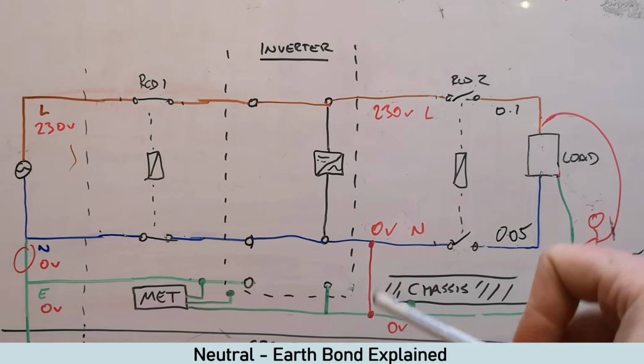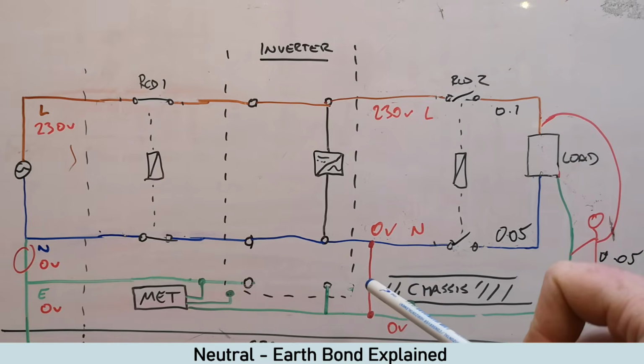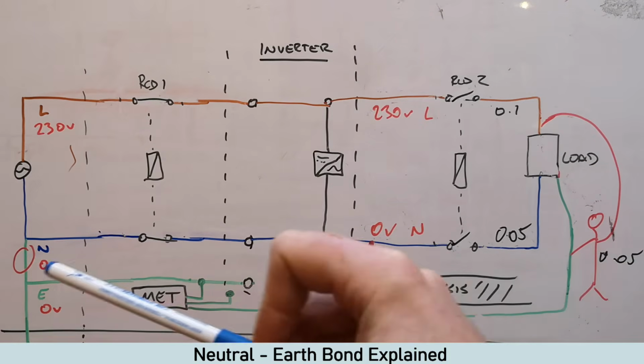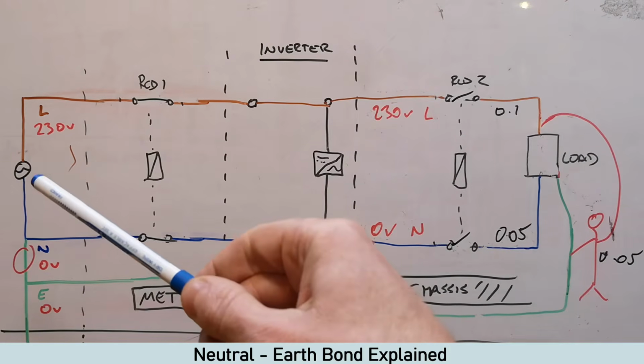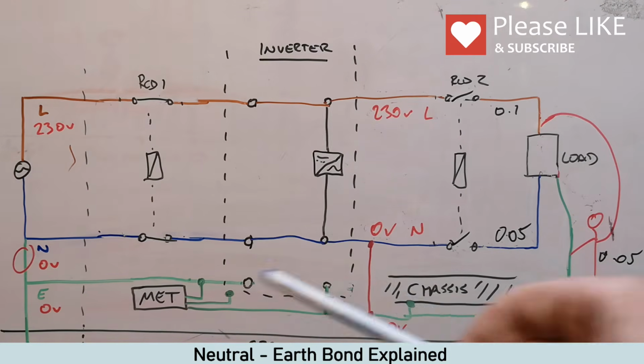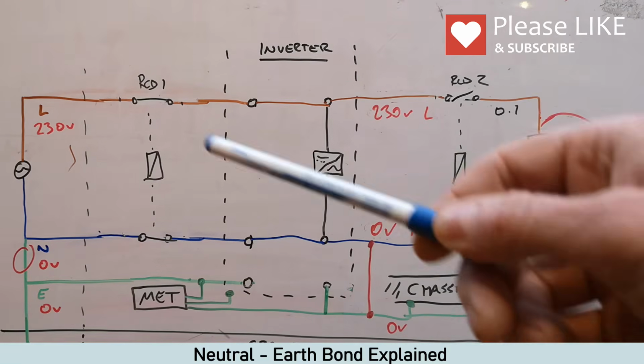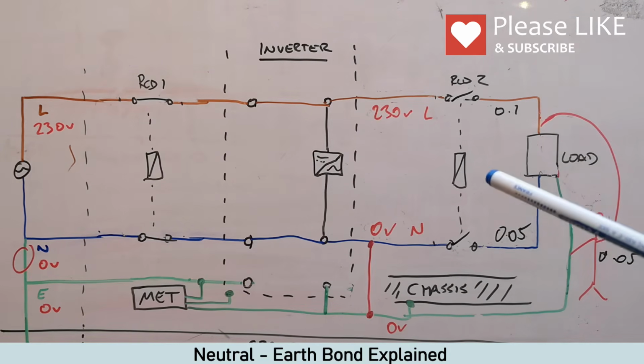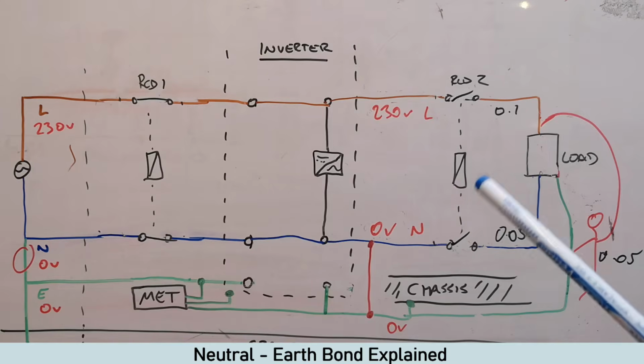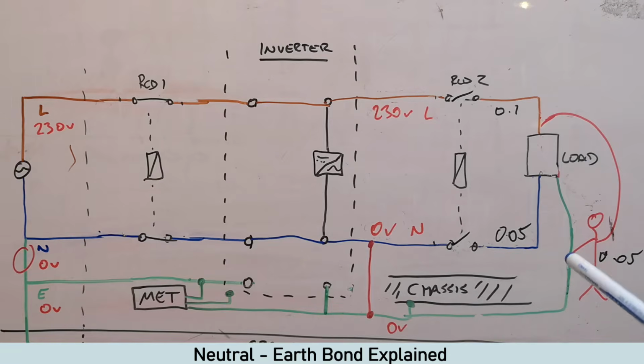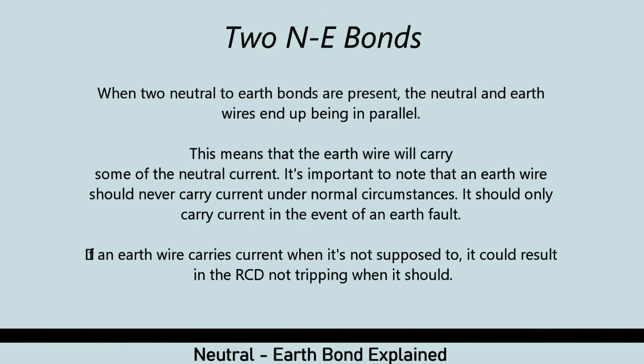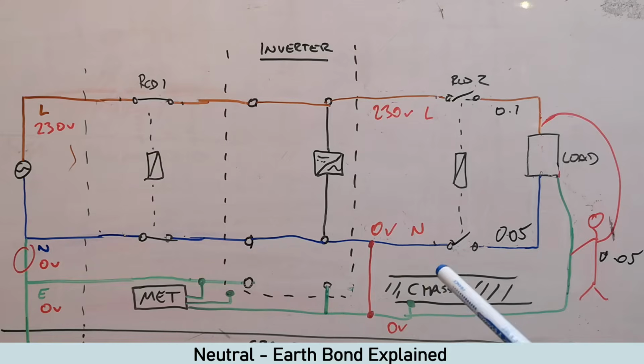Now this is what's going to cause an issue in this system, because you can't have 2 neutral to earth bonds in one system. So obviously power's coming in, you've got 2 neutral to earth bonds. This will cause an issue for the RCDs, so it could involve nuisance tripping, or it could actually affect the tripping when this situation occurs, when there's like a live to earth fault or somewhere. So what needs to happen when on hookup, this needs to come out.